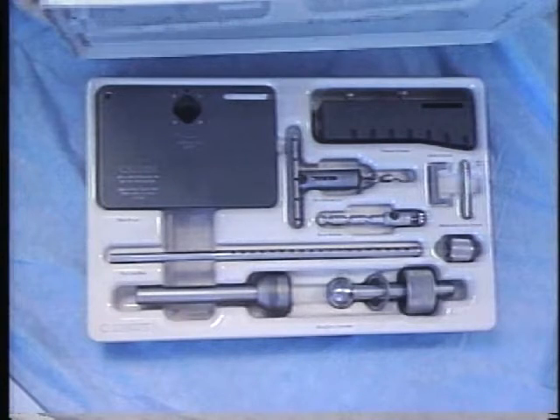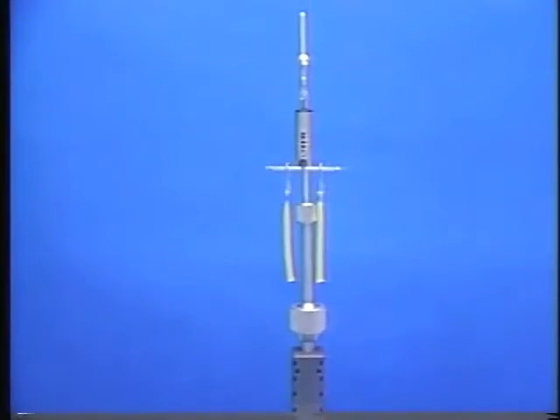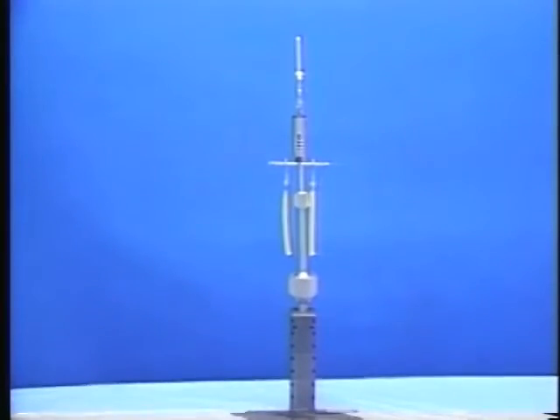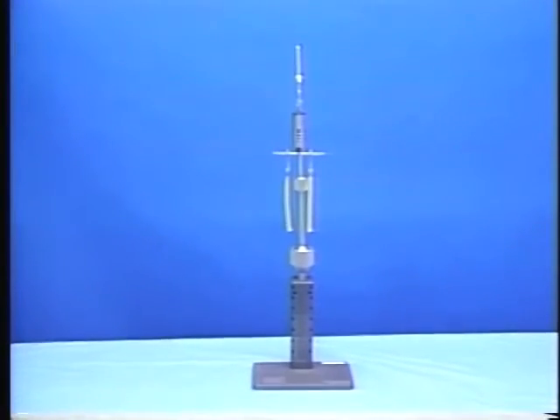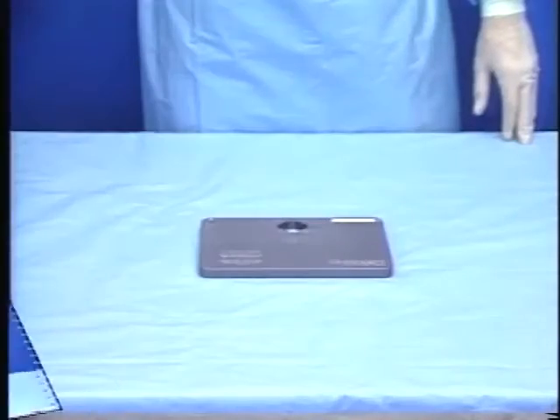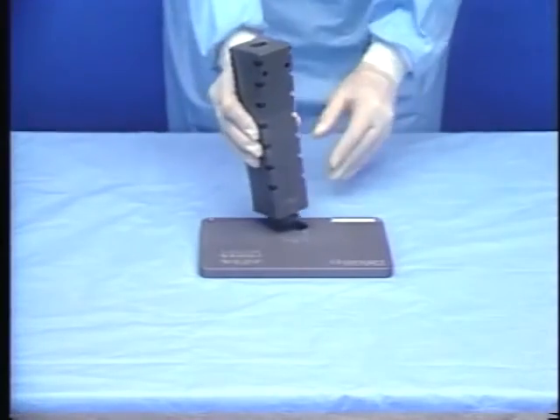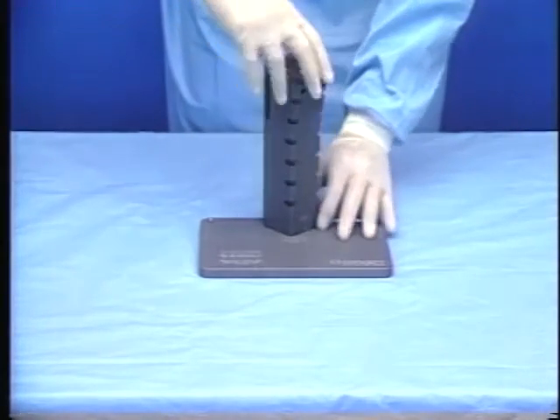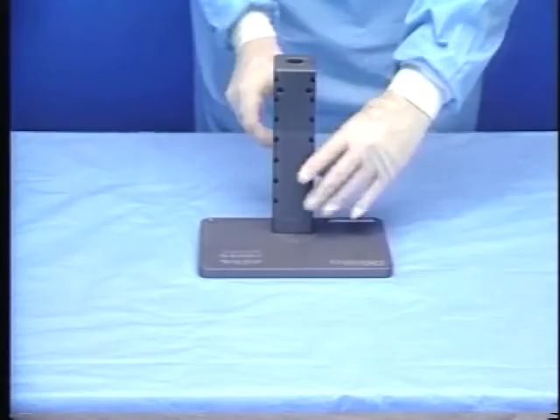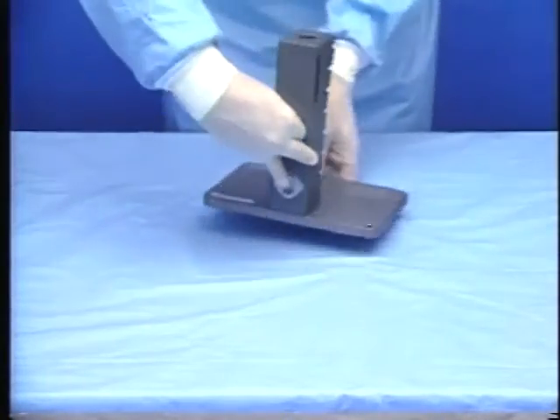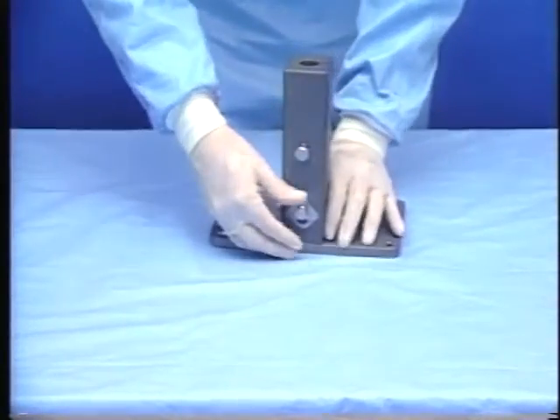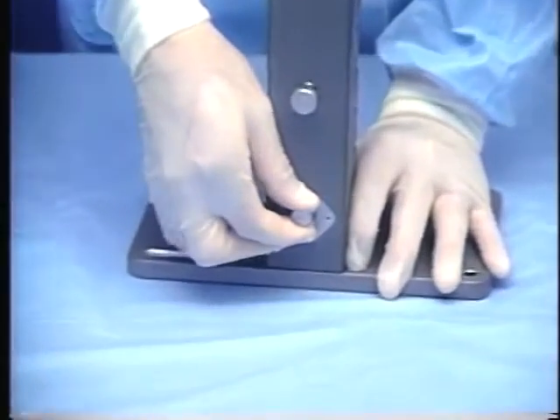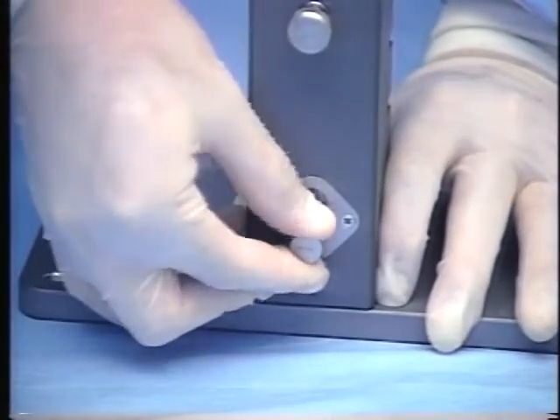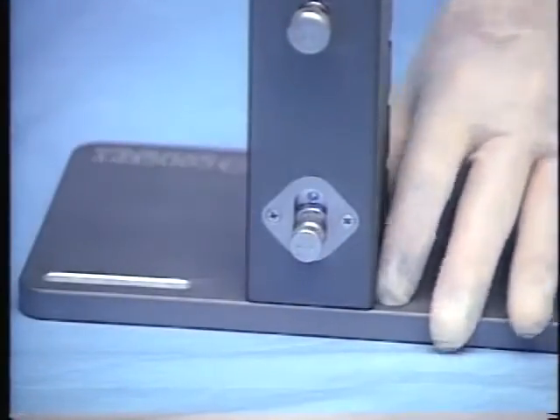Since the traction tower has significant mass and can retain heat, it must be allowed to cool prior to contacting the patient. Assembly of the sterilized components begins with a base plate. Next, the primary support is inserted and twisted clockwise. To lock the primary support into place, the locking pin on the back side of the primary support is engaged.